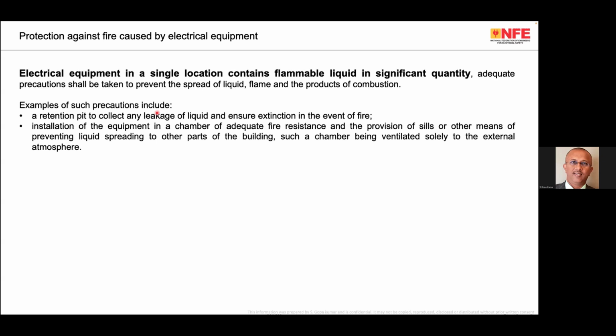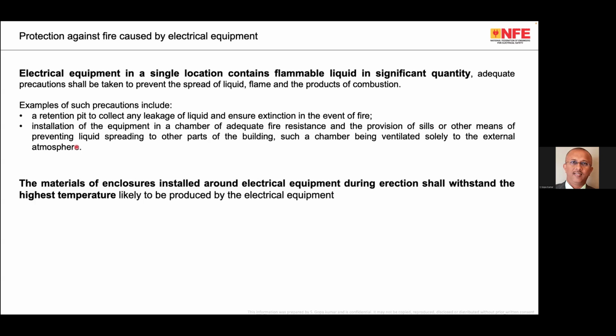Consider electrical equipment in a single location that contains flammable liquid in significant quantity. The quantity referred to is 25 liters. So if equipment contains more than 25 liters of flammable liquid, we have to ensure that necessary measures are taken so that the liquid does not increase the chance of fire. And the equipment in and around the installation, let's say during installation you are welding, shall be able to withstand that particular installation process.